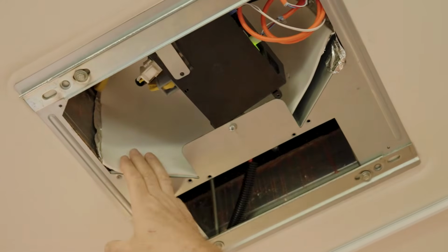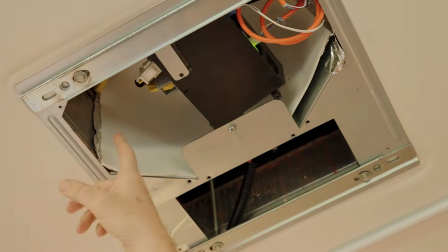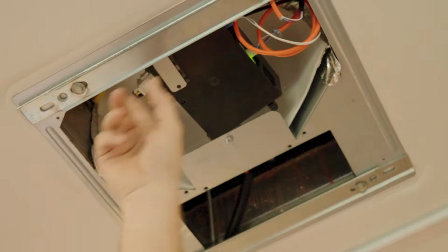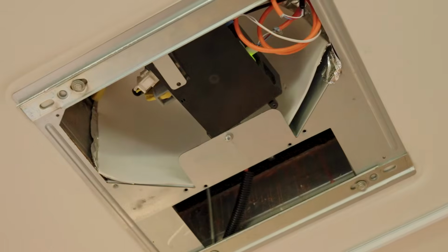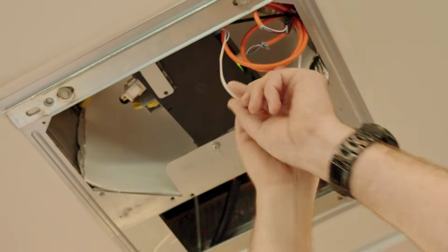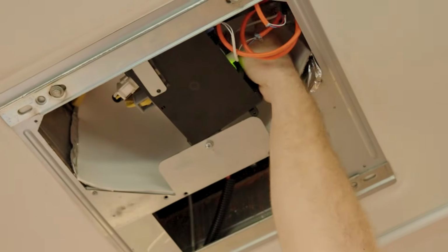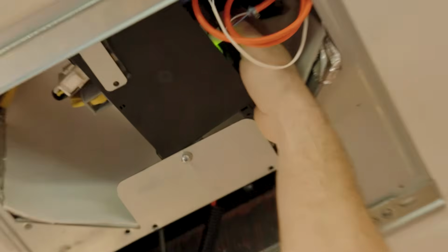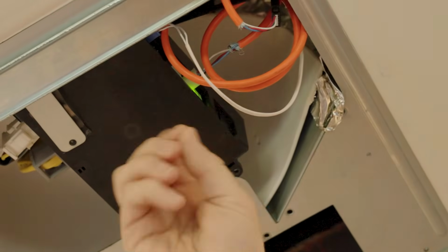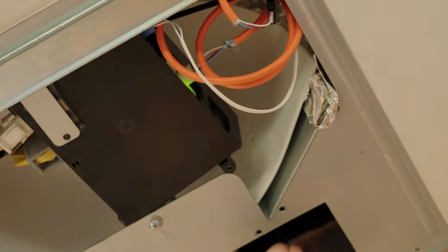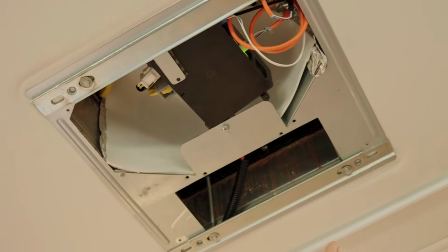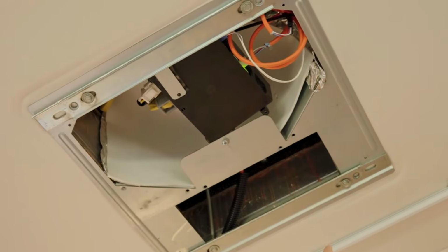If you want to put the foam back up there, go right ahead. Also look for any other things in here that has holes in it. Number 2, look for this freeze sensor wire that comes out of the box. It will go all the way up into the coil. Make sure that is installed. It's just a little wire that actually turns the compressor on and off so it cycles properly. So all those things have to be done before you install the kit.